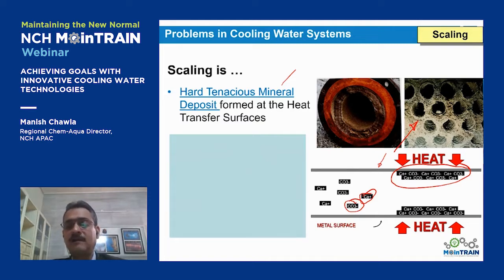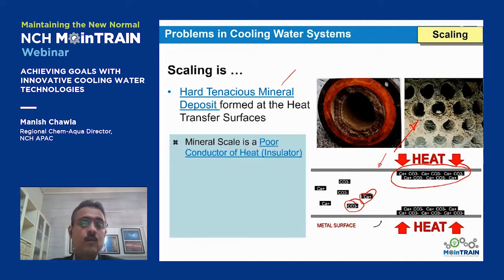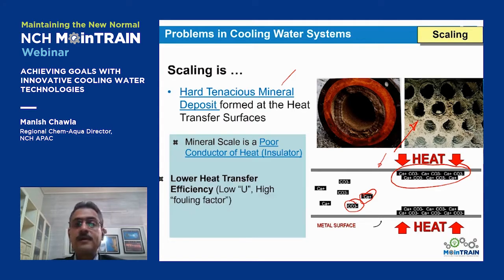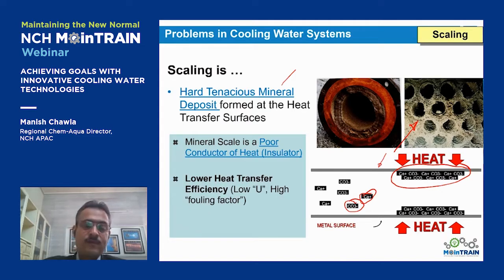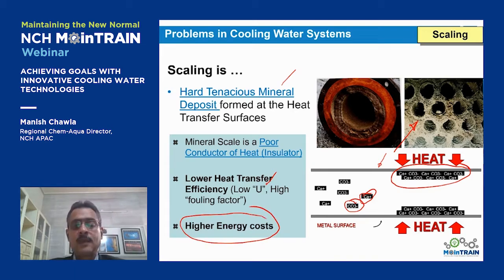Is it good or bad? It is bad, because scale is a poor conductor of heat—heat cannot transfer through it. This heat exchanger was made to transfer heat, but once the scale forms, it cannot do the job it was designed for. So the overall heat transfer efficiency, or overall heat transfer coefficient, will reduce. In the end, what does it mean to us? Higher energy cost.